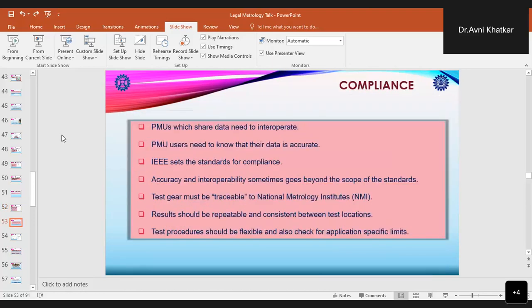So when we talk about this, we talk about the compliance also. All these PMUs which share data need to interoperate, and all the PMU users need to know that their data is correct. So IEEE sets the standards for the compliance. All the accuracy and interoperability sometimes goes beyond the scope of the standards. So test gears must be traceable to the national measurement institutes, and the results obtained should be repeatable, and they should be consistent between test locations. And the test procedures should be flexible, and they should also check for application specific limits.